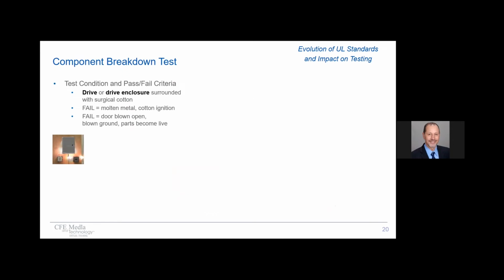And a test is considered a fail when the surrounding cotton ignites, when there is molten metal on the exterior, when a door or cover is blown off, when a ground connection is blown, or when a touch surface becomes live. Now, this is most difficult to pass when a drive is mounted standalone by itself. However, based on the type of protective device used, there are solutions for this type of installation.